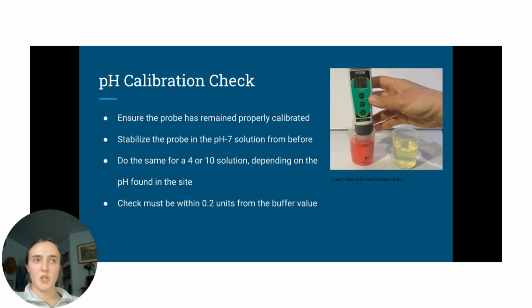The post-sample check needs to be within 0.2 units from the buffer value. For instance, for the pH 7 solution, the post-sample check needs to be within 6.8 and 7.2. If it is between these numbers, that indicates it maintained proper calibration within the field, and we can use the pH data that we got.